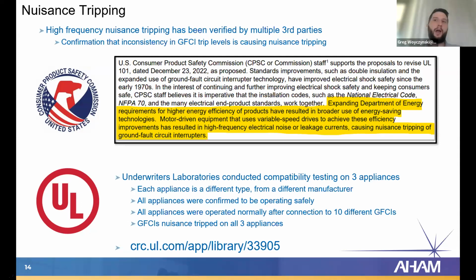They took 3 different appliances from 3 different manufacturers, connected them to 10 GFCIs, and GFCIs nuisance tripped on all 3 of those appliances. All of those appliances were confirmed to be operating in a safe way by UL, by any measurement you can think of, but GFCIs tripped on all of those appliances. And this is the link. Again, I'll give my slides to UASA, but this is the link where you can read more about the study if you're interested. Okay.